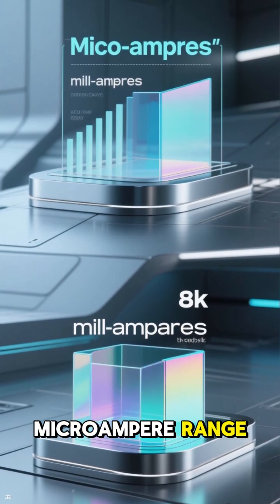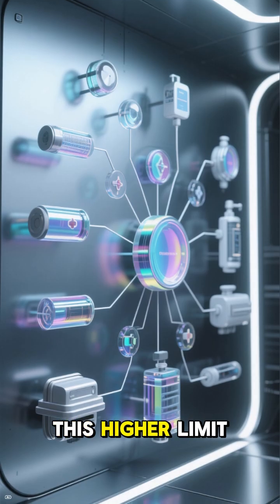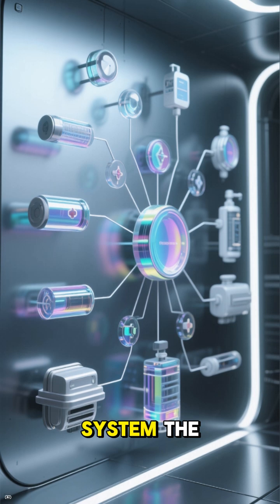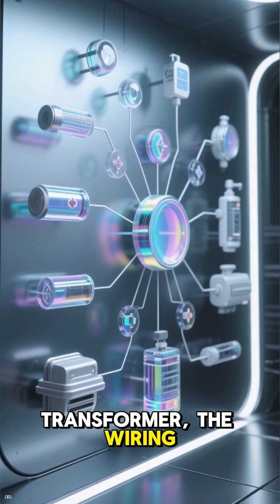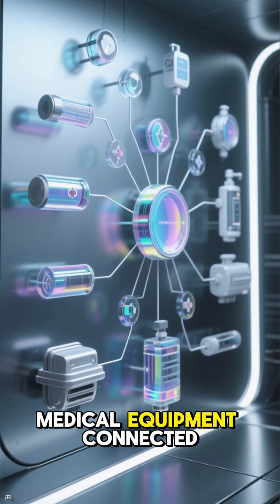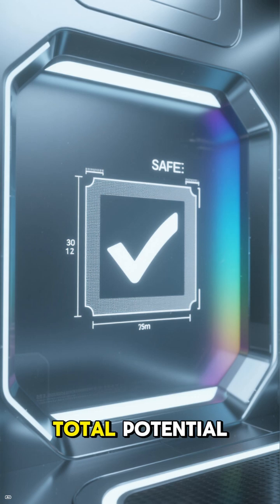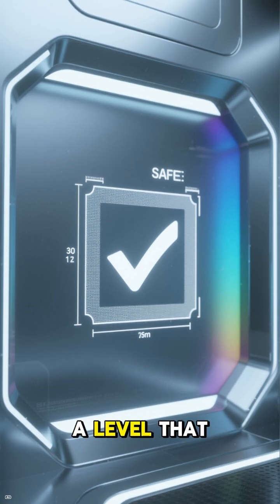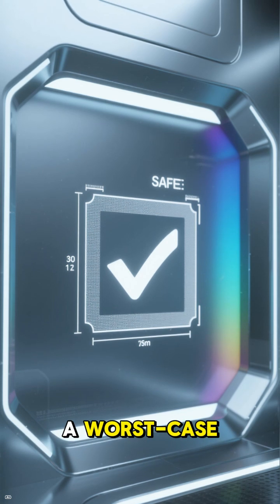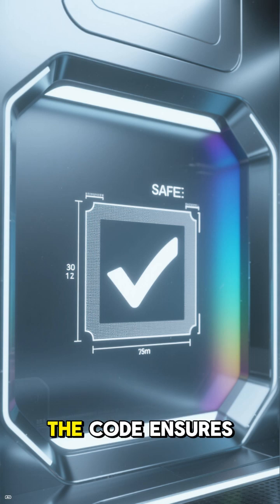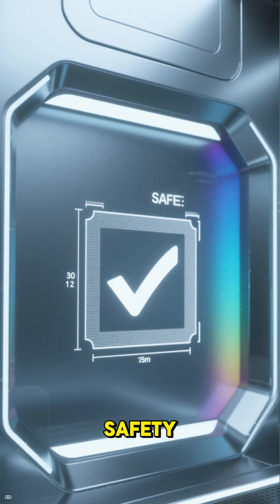While the threshold for microshock is in the microampere range, the total hazard current limit is set in milliamperes. This higher limit accounts for the entire system, the transformer, the wiring, and every single piece of medical equipment connected to it. By keeping the total potential leakage well below a level that could cause harm even in a worst-case single-fault scenario, the code ensures a high degree of patient safety.